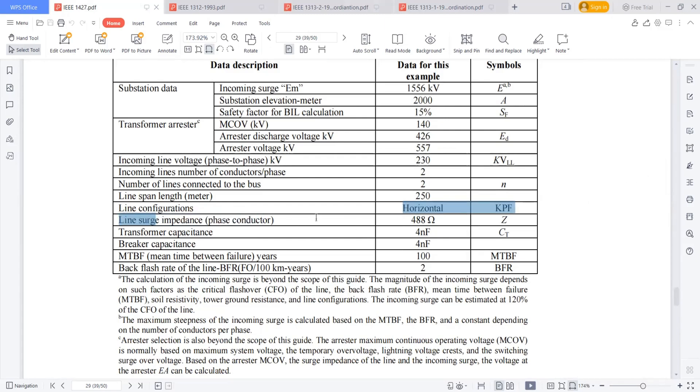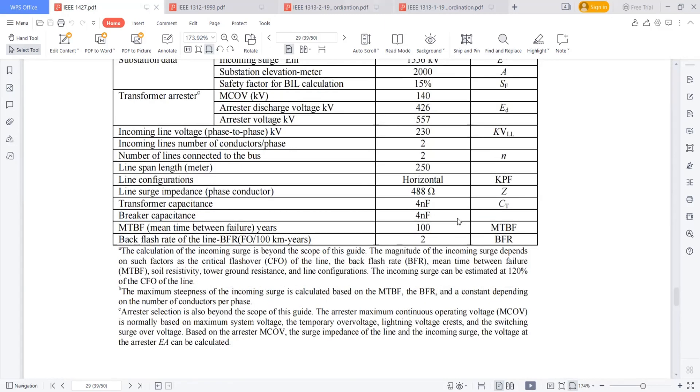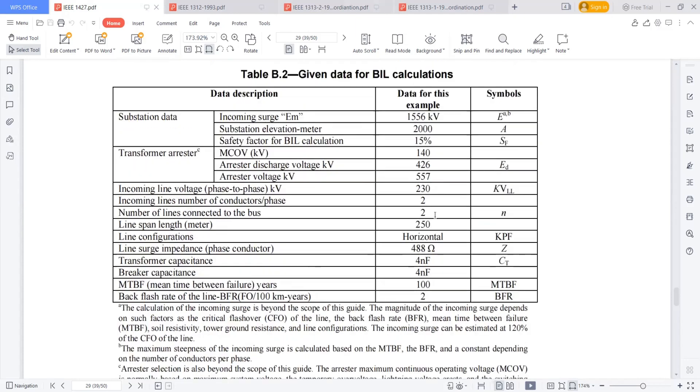What is the line surge impedance? It's again depends on from the transmission line analysis. They will get 488 ohms. And this transformer capacitance, breaker capacitance, mean time between the failures, back flash over rate. All these things you will get from the manufacturer and from the IEEE part two. So these are some inputs I required to do this calculation.